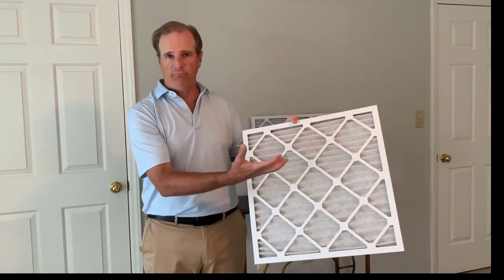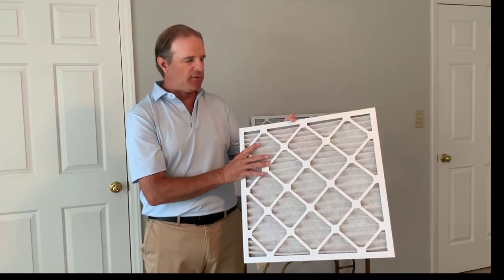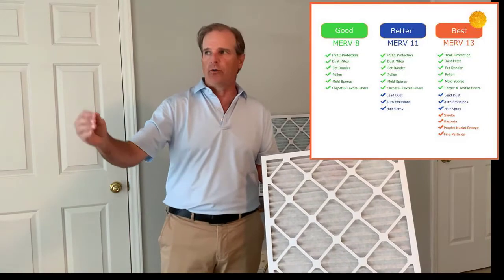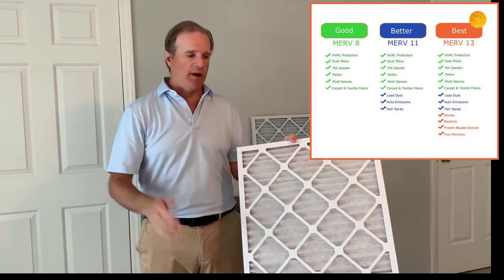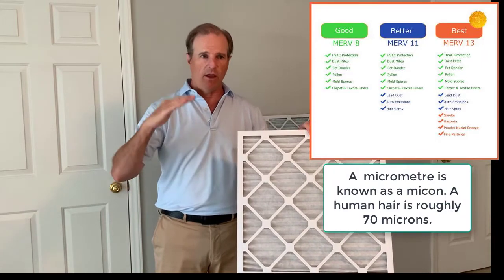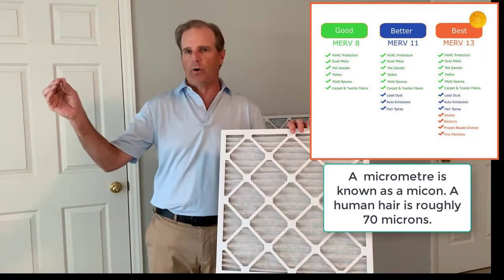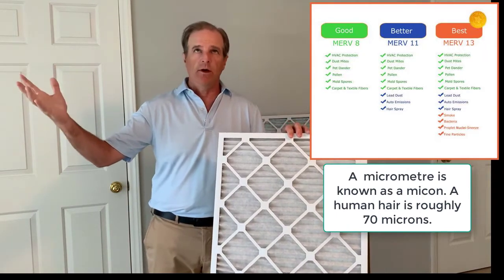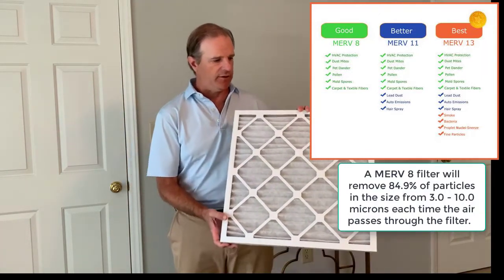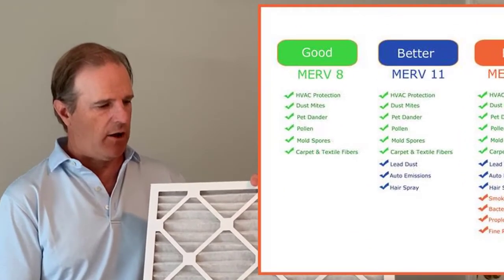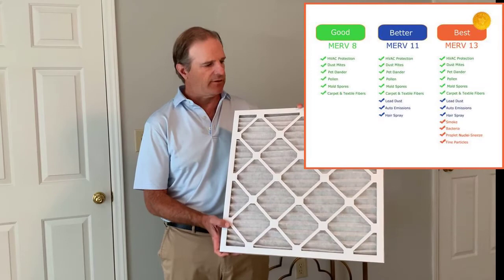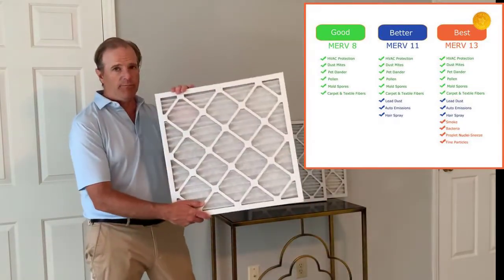The way to evaluate one filter brand against another is to look at efficiency. MERV 8 filters particles generally in the range of 3 to 10 microns. A micron is a very small measurement — roughly 70 microns is the size of a human hair. So we're talking about small particles like dust and dust mites, which is what MERV 8 filters out. They also filter out pollen, lint, and some larger particles. This is a good beginner level of filtration.